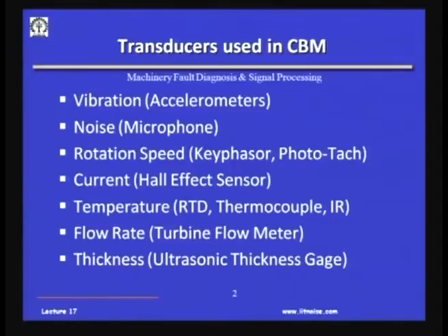And then next comes temperature. Temperature, I do not mean the temperature of a human being here, but the temperature of machineries, of bearings, of oil baths in the gearboxes, and these temperatures could be very high. Imagine the temperature of a blast furnace. Inside a blast furnace, I possibly cannot stick in a thermometer. So, we have to use certain non-contacting type sensors like infrared sensors or pyrometers, and for a high range of temperature, perhaps thermocouples or RTDs, resistance temperature detectors.